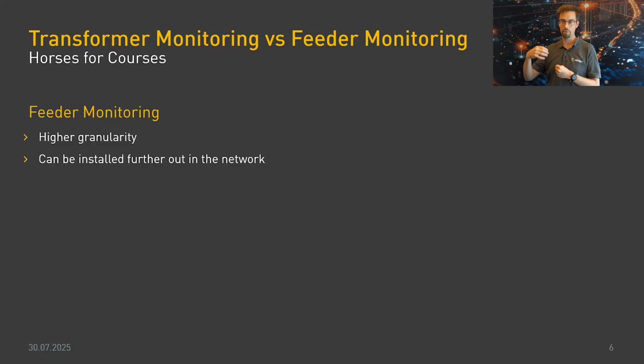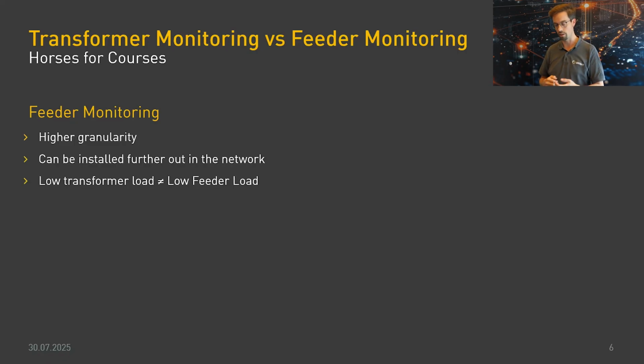The other thing is some of the critical points might actually be further out in your network. Transformer monitoring can only be done at the transformer, but sometimes I want to know what's happening at the end of a voltage line, at the end of a feeder, and that's particularly important for voltage. The voltage that you're seeing at the substation is going to mainly be dictated by the medium voltage. Whereas if you've got solar feed-in, or if you have particularly high loads, your voltage drop or your voltage rise, you're going to see at the end of the line. And so it can be very useful to actually take those measurements further out in the network. That's where feeder level monitoring can really be very useful, when you want to take those kinds of measurements.